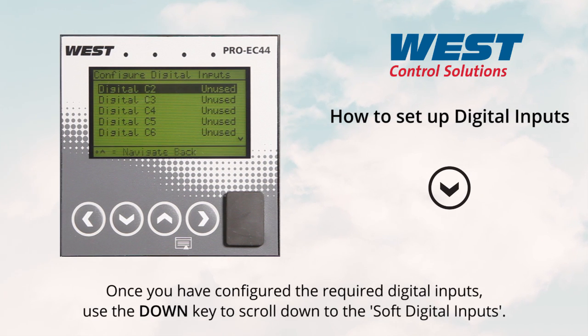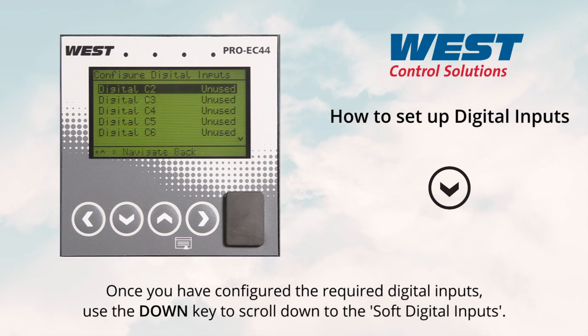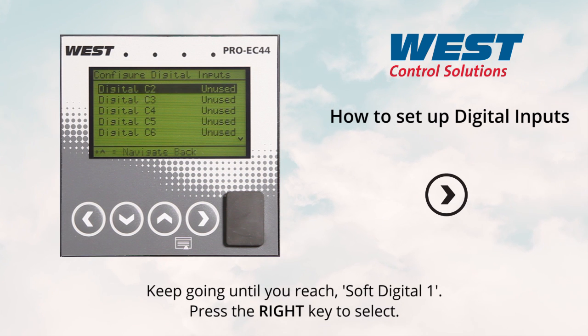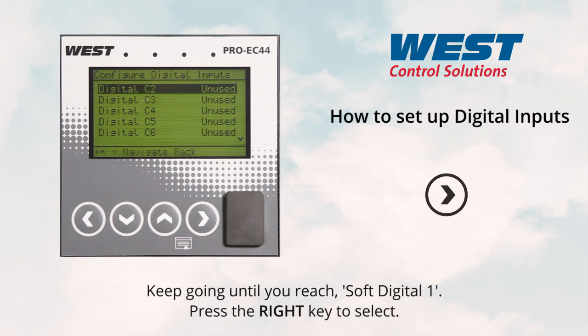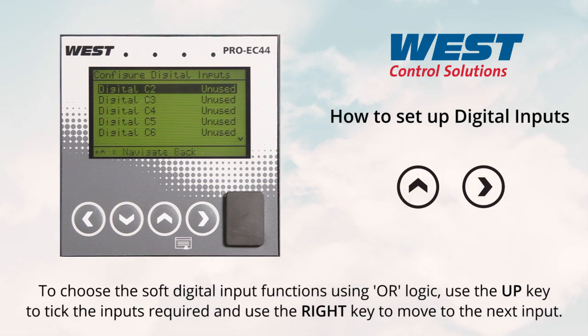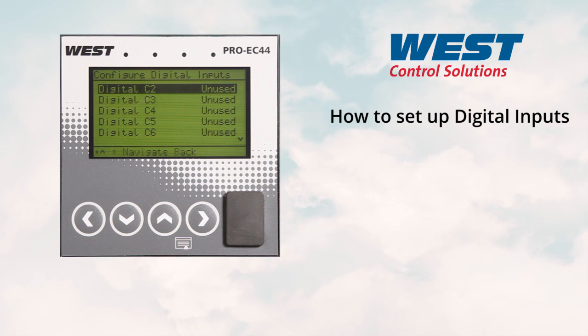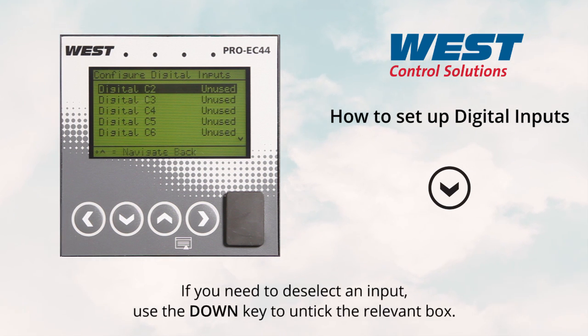Once you have configured the required digital inputs, use the down key to scroll to the soft digital inputs. Keep going until you reach soft digital input 1, then press the right key to select. To choose the soft digital input functions using OR logic, use the up key to tick the inputs required and use the right key to move to the next input. If you need to deselect an input, use the down key to untick the relevant box.